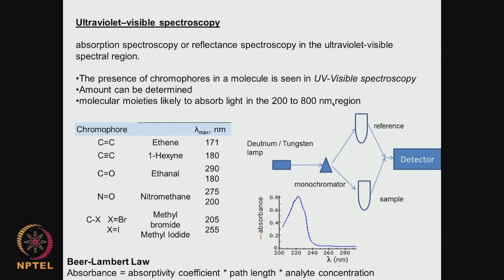Generally when we talk about UV and visible, we are talking in the region 200 to 800 nanometers. The instrument has a deuterium tungsten lamp, then a monochromator, and the light passes through the sample and is detected. We have a reference, and with respect to the reference we can monitor whether a chromophore is present and at what concentration. The spectrogram shows a peak at a particular lambda max, which is characteristic of the type of chromophore present.